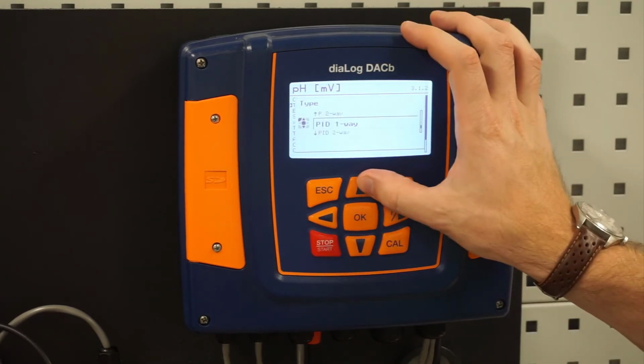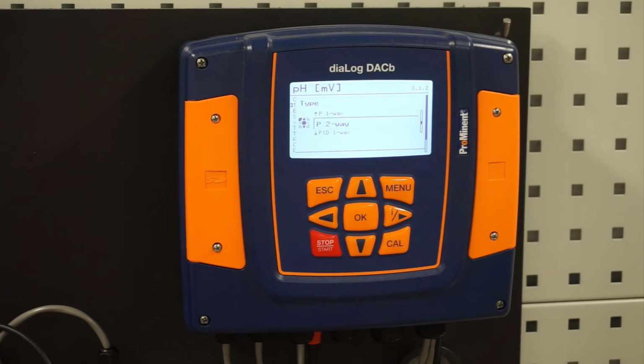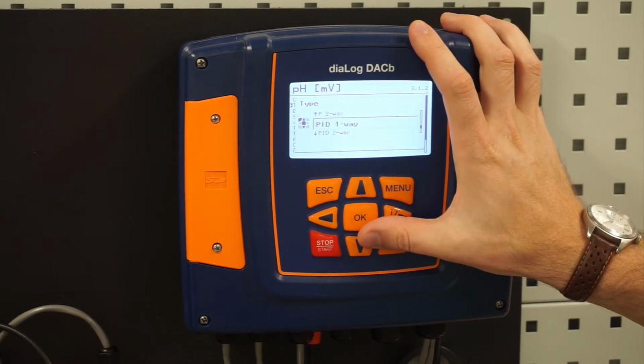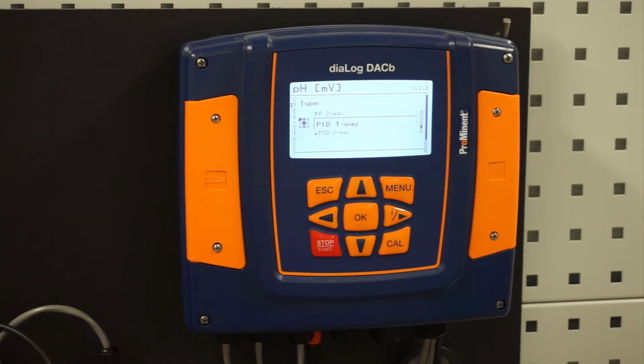I'm not going to go very in depth in this. That would be a whole other video that would take some time discussing what proportional control is versus full PID control. But you have that ability to do full PID in here. If I were to set up PID with this, I'd have very tight control over my process with the chemical injection. One way would be for pH putting either just an acid in or a caustic in. Two-way would be me doing both. So maybe I have an acid pump and a caustic pump. Most likely it's going to be one way.